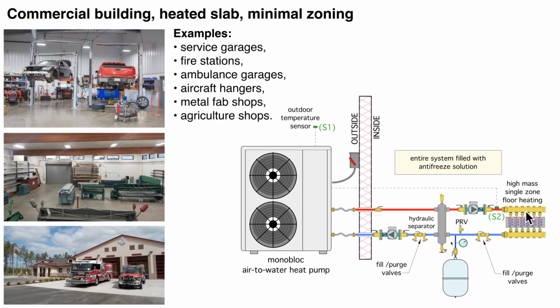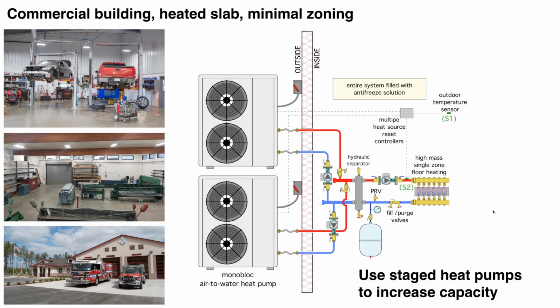So you can do constant circulation over here and just simply have the heat pump turn on and off or modulate to control the supply water temperature going to the floor. You can do that with outdoor reset control. That will keep the heat pump operating at the lowest temperature that will still adequately heat the building. The lower you can keep that temperature, the higher the COP of the heat pump is going to be.